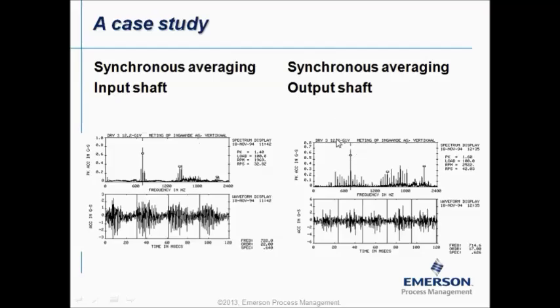However, exactly the same measurement point, but now the photo tach pulse is connected to the output shaft, we see the gear mesh and a lot of side bands. So all the energy is coming from the side bands, and in reality this was because there was severe wear on the output gears.